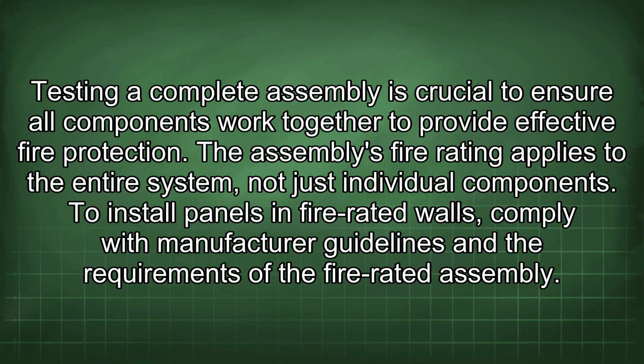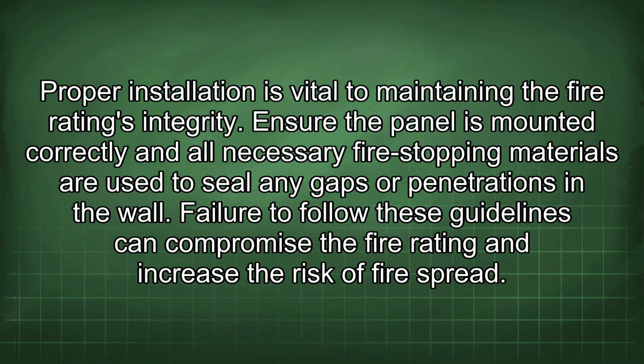To install panels in fire-rated walls, comply with manufacturer guidelines and the requirements of the fire-rated assembly. Proper installation is vital to maintaining the fire rating's integrity. Ensure the panel is mounted correctly and all necessary fire-stopping materials are used to seal any gaps or penetrations in the wall. Failure to follow these guidelines can compromise the fire rating and increase the risk of fire spread.